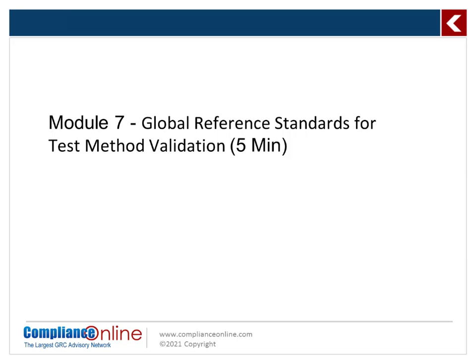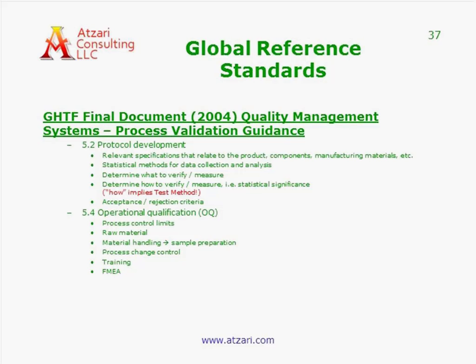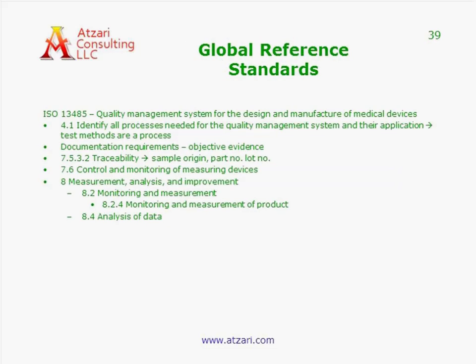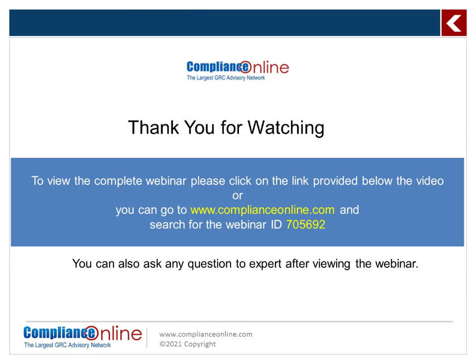Another excellent standard — actually preferred — is the global harmonization standard for process validation guidance, which gives you almost everything you need for validating not only a process but also a test method. Remember: the counterintuitive logic is that you're measuring the variation of the measurement system as opposed to the process. There is also ISO 13485, which, even though it's for quality management systems, talks about traceability, control of measuring devices, measurement, analysis, and improvement — all of which applies to your test methods.